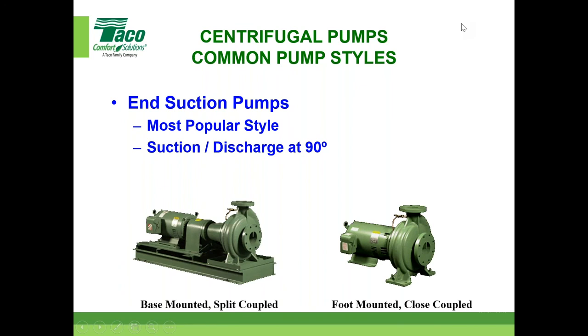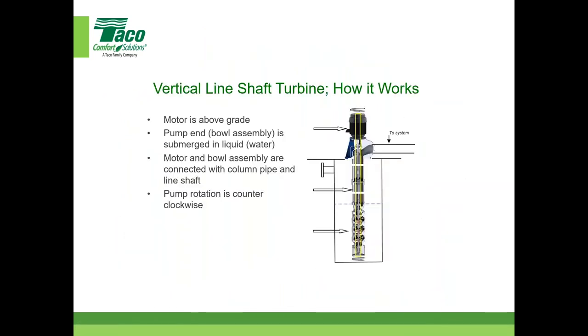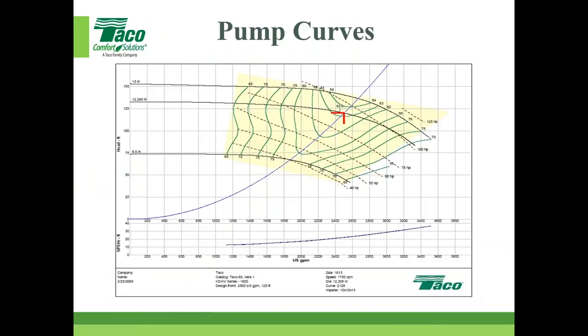Correct, Rich? Yes. So one thing that we always have to make sure of is, remember, most gauges in the field are measuring the pressure in pounds per square inch gauge, but we publish the pressure differential for the pump in feet of water column, and the conversion is 2.31 feet per pound per square inch. So if you had a discharge pressure, say, of 30 pounds per square inch gauge, and a suction pressure of 20, the differential would be 10 pounds per square inch. You would have to multiply that by 2.31. So 10 times 2.31 is 23.1.